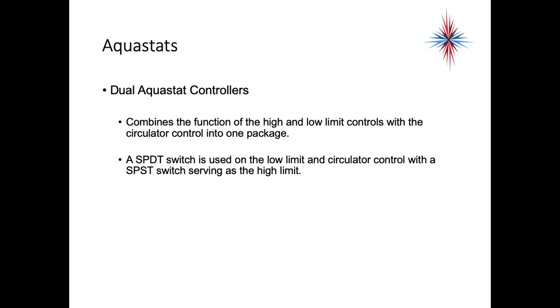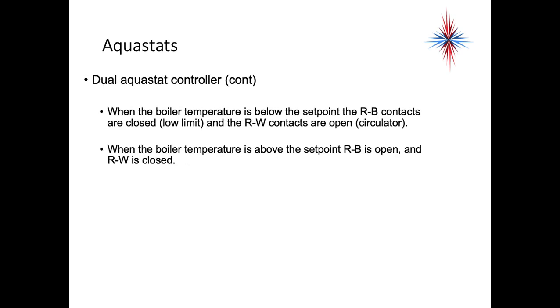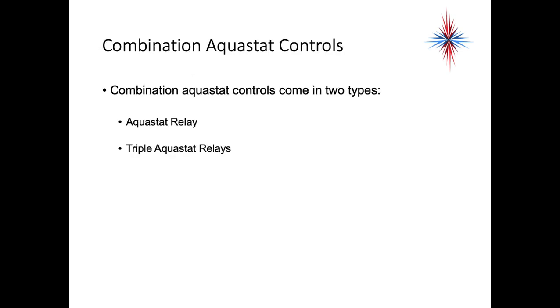Dual aquastat controllers combine the function of the high and low limit controls with the circulator control in one package. A single pole double throw switch is used in the low limit and circulator control, with a single pole single throw switch serving as the high limit. When the boiler temperature is below the set point, the R and B contacts are closed — that's the low limit side — and the R and W contacts are open — that's the circulator side. When the boiler temperature is above the set point, R to B is open and R to W is closed for the circulator.